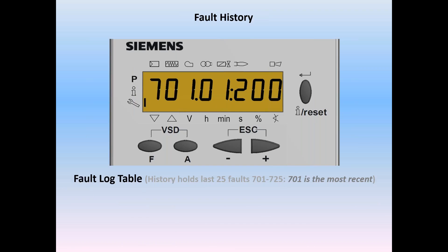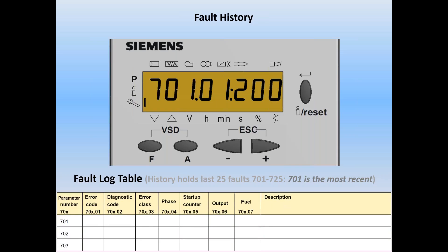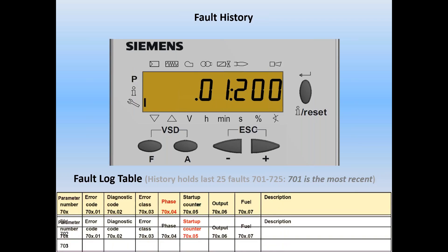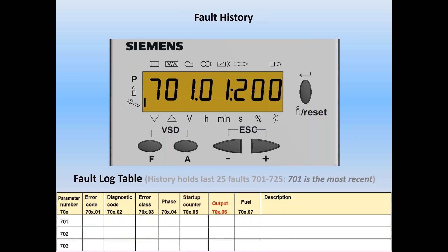The history holds the last 25 faults, parameters 701 to 725. Parameter 701 is the most recent fault. In the fault log table, the columns are: parameter number, error code (index 01), diagnostic code (index 02), class (index 03), phase (index 04), start counter (index 05), output or firing rate (index 06), and — if equipped with dual fuel — LMV36 fuel type (index 07, value 0 or 1). Then we can add our descriptions.